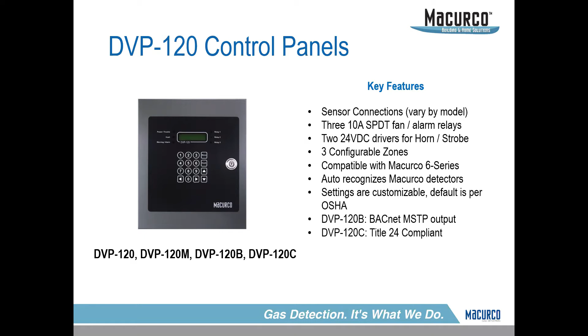So our innovation is up to date. And in fact, it was released last month with DVP 1200. What this product is, it's an expandable panel of up to 192 sensors. Prior, we were only able to do around 99 as a full system. So when you're talking your high rises, you're talking your massive Amazons, your UPSs. I know out in the Central Valley in California, there's UPS and Amazons popping up pretty much everywhere. Those type of facilities that are hundreds of thousands of square feet, this would be the type of panel you would use.